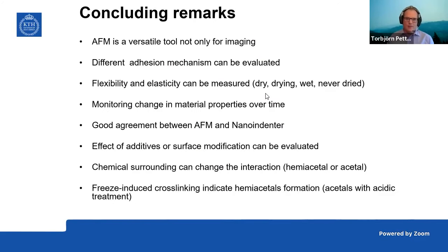As concluding remarks, I want to stress that AFM is a versatile tool, not only for imaging. We can do force measurements and understand interactions. Different adhesion mechanisms can be evaluated. Flexibility and elasticity can be measured in the dry state, during drying, in the wet state, or in never-dried material. We can also monitor changes in material properties over time, like during drying. We get good agreement between AFM and nanoindenter.